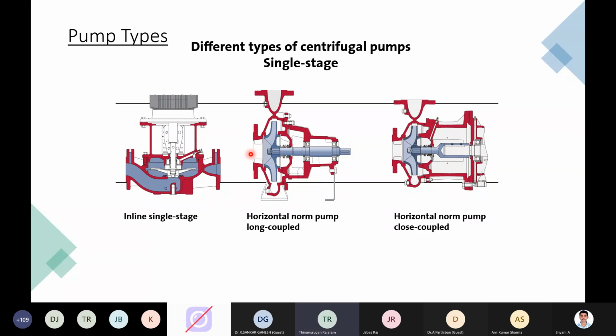because of cavitation or because of excess vibration, or the pump not operating in a particular zone, what gets hit first is your mechanical seal and bearings, because these are very sensitive parts in the product that can easily get affected. So we always recommend operating the pump for its intended purpose, its intended operating situation. That is more important. Okay, and after that you have a coupling and a motor.